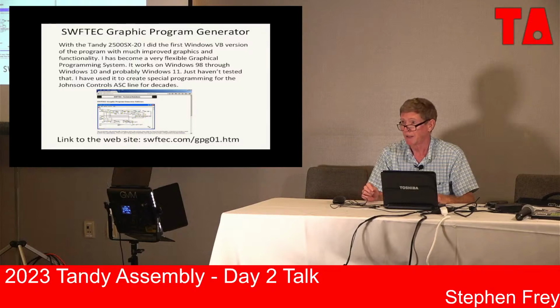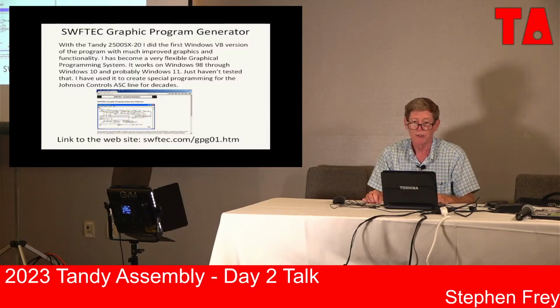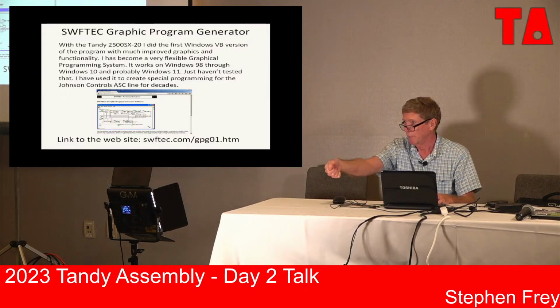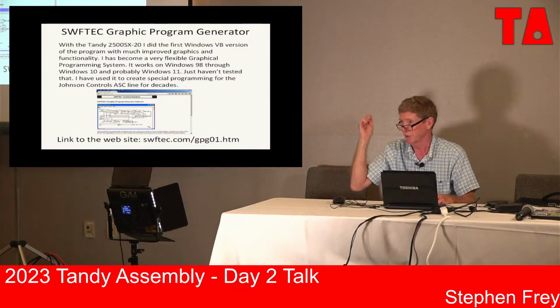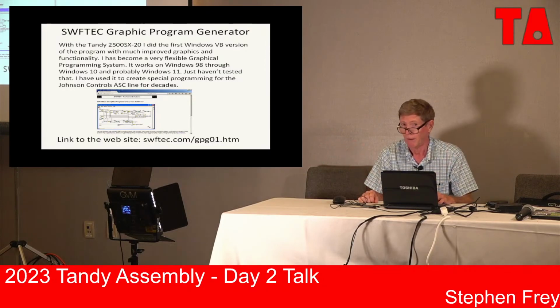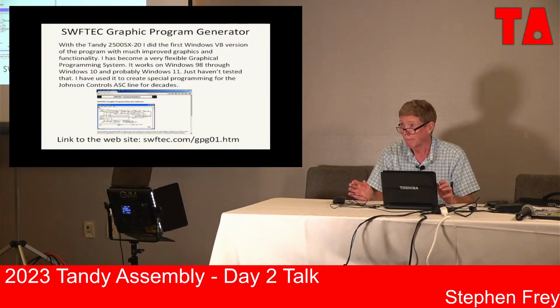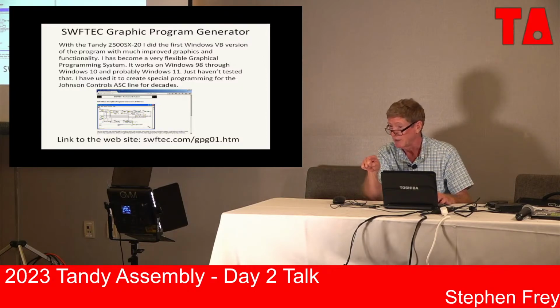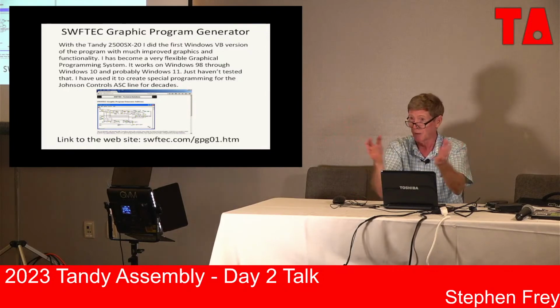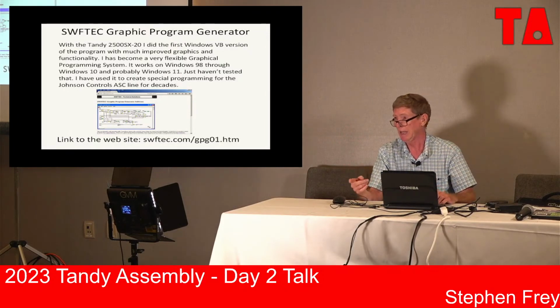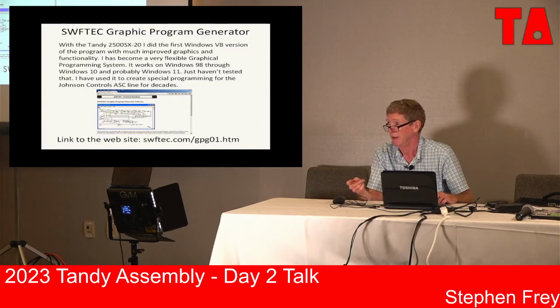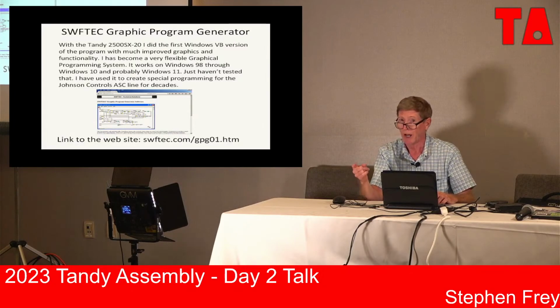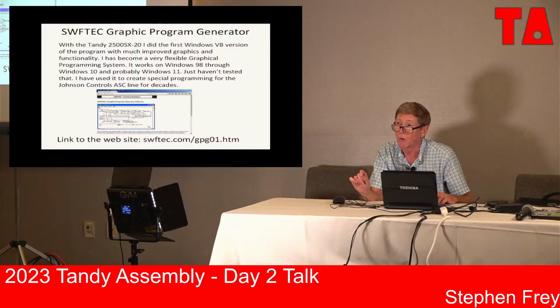An example from one of the demonstrations I did - I did a lot of demonstrations - I could walk up and pull off a temperature sensor or pressure sensor while this thing is running, and it kept right on running. It reported, this is what the sensor says, but I think the real pressure or temperature is this, because it's using everything else in the model to figure out what it has to be. So it automatically keeps operating even though that sensor's not working anymore. Just think about how powerful that is.